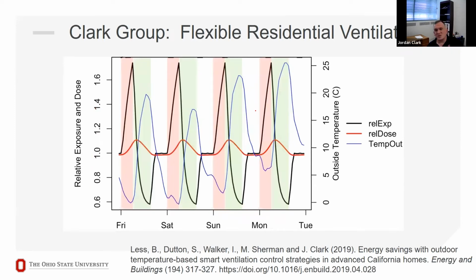We've explored how we could do this with ventilation as well. This has got a lot going on, I'll try to explain it real quick. The blue line is showing the outdoor temperature - basically at nighttime it gets cold, daytime it gets warm. Our ventilation energy required is proportional to the temperature, so if it's really cold outside and we're bringing in a bunch of cold air for ventilation, we're going to have to heat that up - it's an energy intensive process.